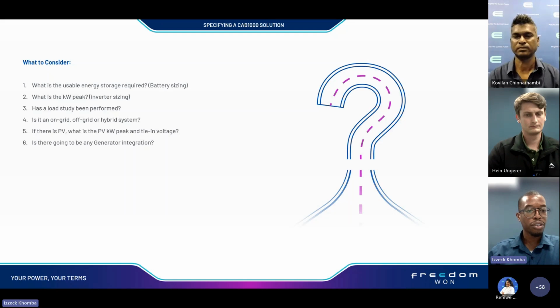Then if you've got an on-grid or off-grid hybrid system, it translates to what will be integrated with the CAB. If there are any other external sources, such as your grid-tied inverters, your wind turbine, or your generator integration, we need to understand how those are going to be integrated in order to design the system to function as a hybrid. Then if you've got PV, obviously we need to understand the kilowatt peak. Normally, if you've got a 1-to-1 ratio, it works quite well, because as soon as you lose control of your grid-tied inverters, you don't have high power that can be injected back into the inverters.